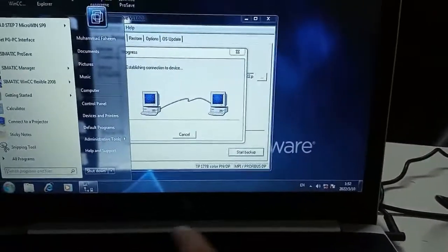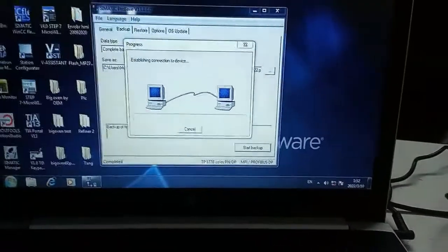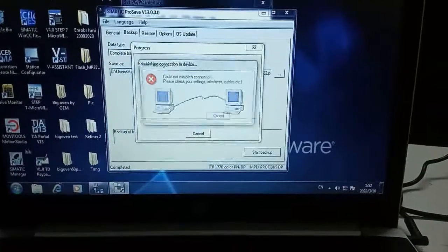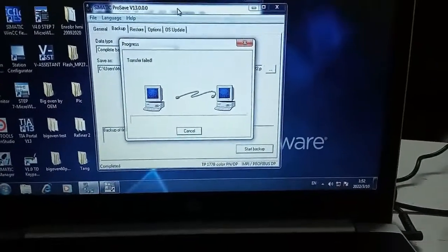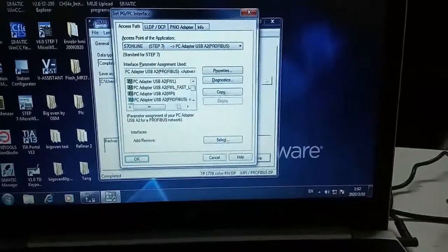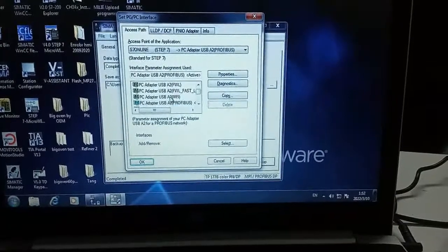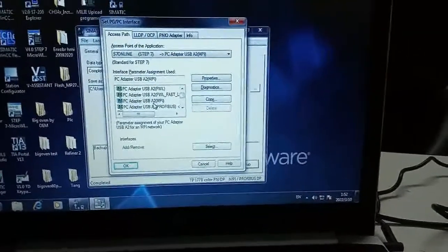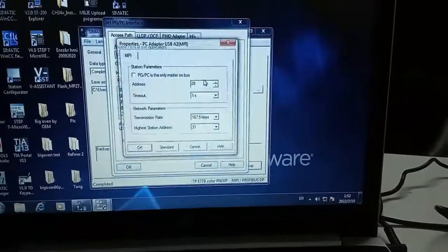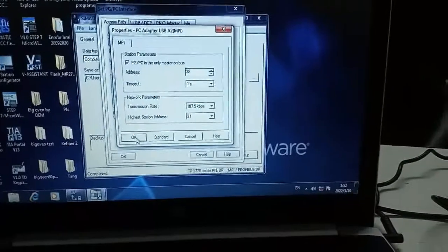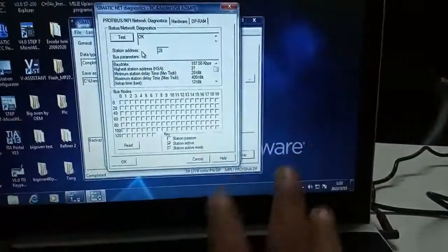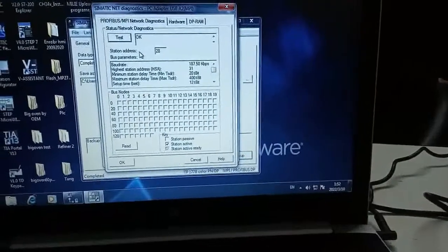Cancel this. Go to the... As I am using MPI cable, that is why select MPI, set PGPC only the master, select OK, diagnose. It gives you the picture of whatever error is present or all the thing is fine.